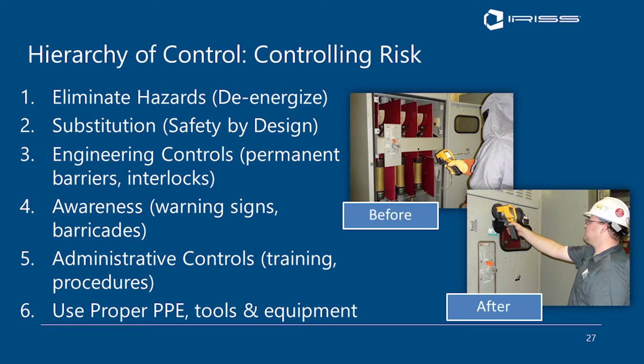So that's number 2. And then you have the engineering controls, which is, can I redesign the work task in such a way as to reduce the hazard? Not eliminate, but reduce the level of hazard. So if I can't eliminate it, can I reduce it in some way? So this is engineering controls, permanent barriers, interlocks, special grounding schemes that reduce the available fault level on the gear, maintenance modes on circuit breakers that you turn into maintenance mode and it reduces the available fault level.